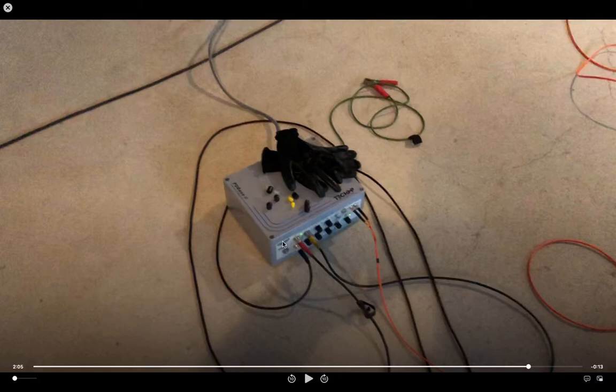Now this is the acquisition unit. The acquisition unit, as you can see, is called PD Base 2. You remember we had from the capacitive coupler two coaxial cables: one was red, and this is the high frequency cable going to channel one. From HFCT we had the yellow cable coming into channel two. And the other cable from the capacitive coupler was a sync cable, and this is the synchronization 50 hertz signal. We still have two more channels, and we also have fiber optic communicating with our computer.